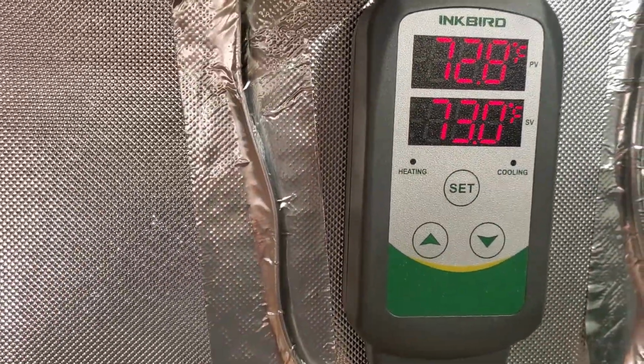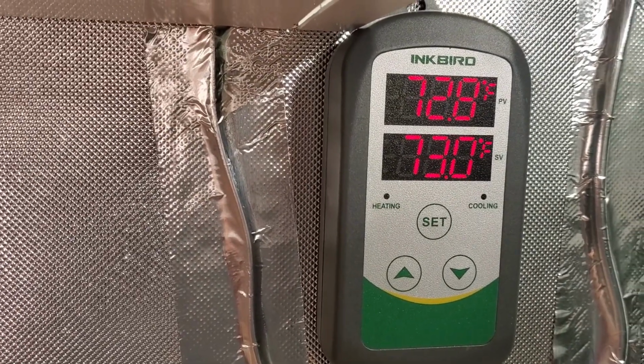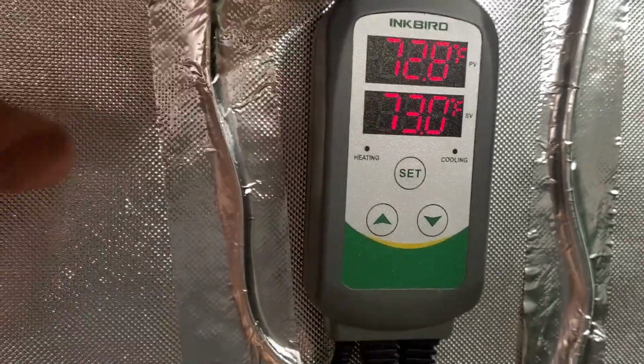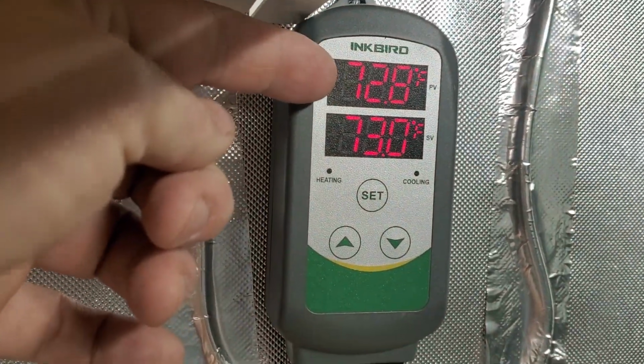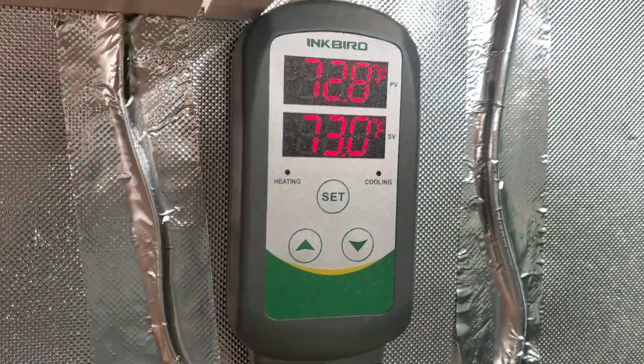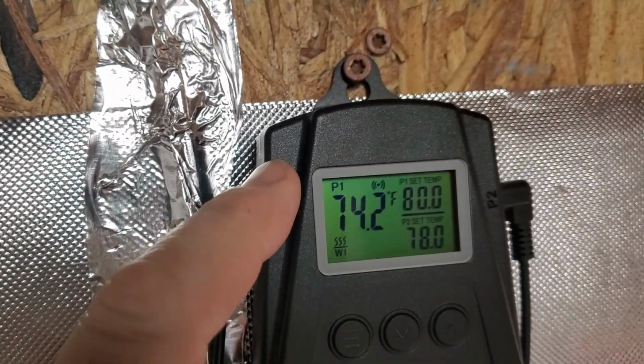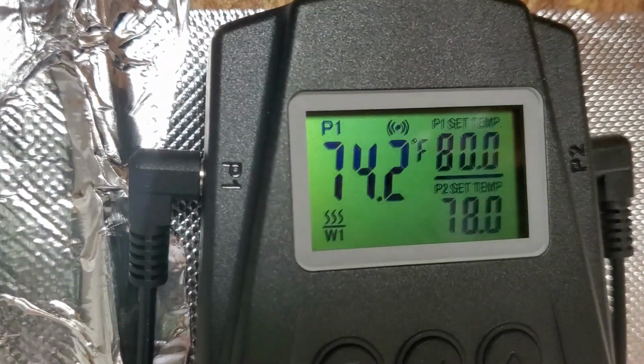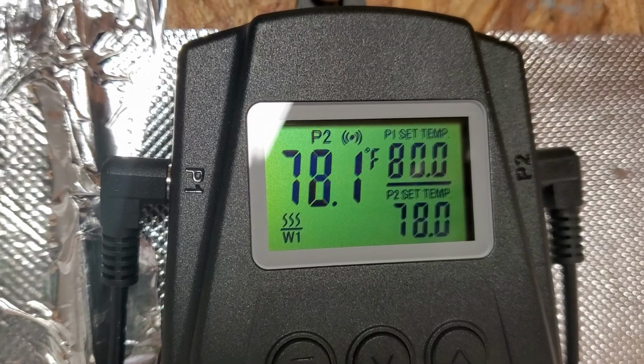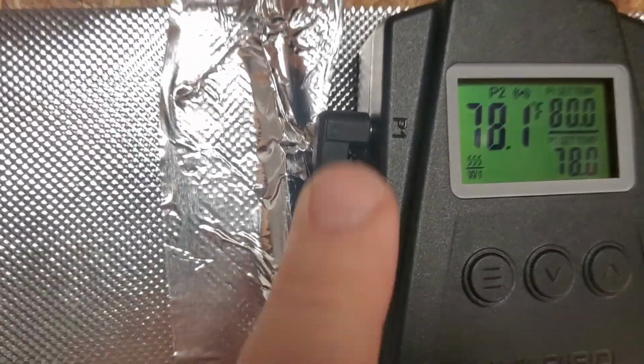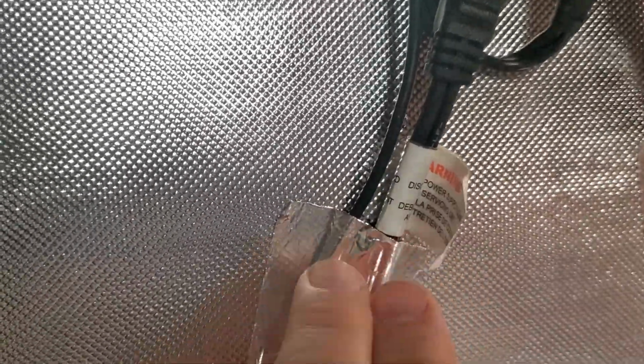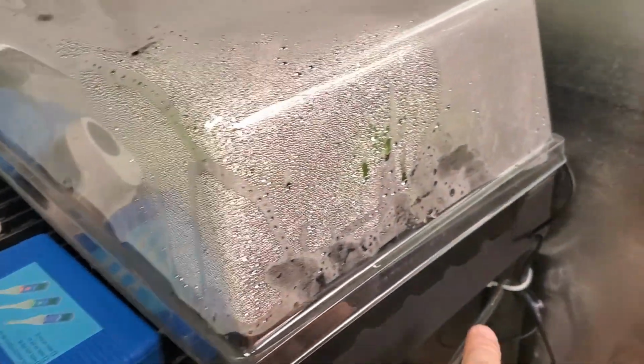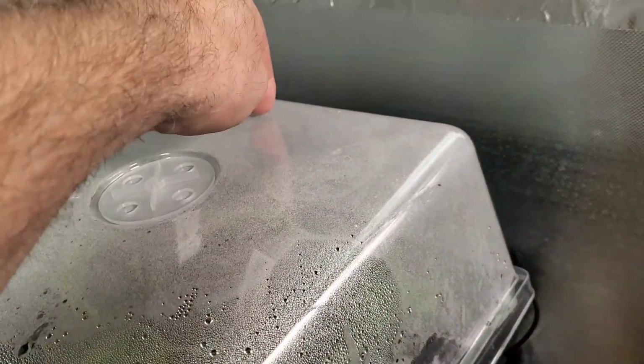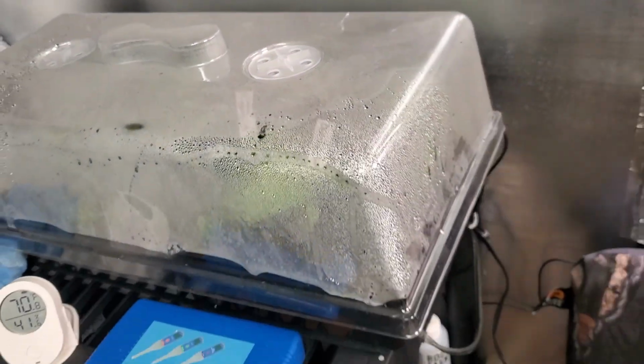As you can see up here, you'll notice that it's showing my set temperature, and up above that is the actual temperature that's currently coming off the probe. Moving over to the star, you can notice that it's toggling between P1 and P2, showing those temperatures. On the right, it shows the set temp for each side, plus down below the W1, showing that that first mat is being heated. You'll notice that I have them running to their corresponding mat. Like below here is the mat, and then over and coming inside of the dome is the probe for an actual temp on what's inside.